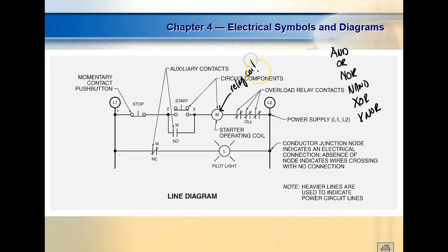Very seldom in industrial controls are you going to see motors, except little tiny motors, inside the control circuit. Why? It's called a control circuit. It's in there to control things, right? You understand? Our motors are going to be high power things. They're not going to be inside our control circuit. Our control circuit is usually going to be a lower voltage. What advantages does low voltage have over high voltage? Safer. And all our high wattage devices are going to be where? Over in what we call a power circuit.